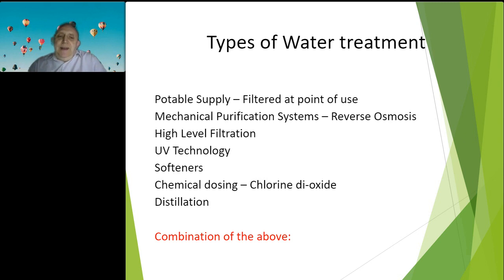We have mechanical purification systems, of which, as mentioned earlier, RO is probably the most common. We have high-level filtration, UV technology, water softening systems, chemical dosing systems. Typically, hospitals, if we're talking about drinking water, will have chlorine dioxide dosing systems at source, where it enters the healthcare facility. We also have distillation plant.